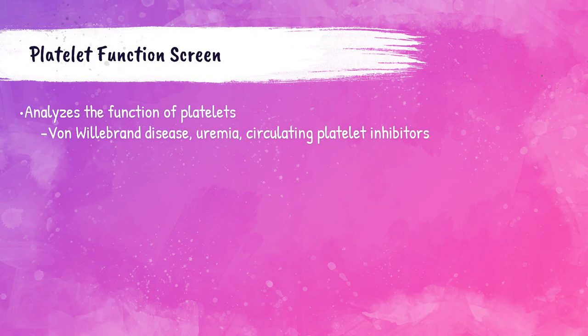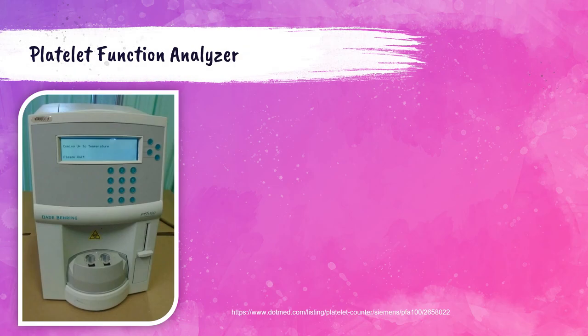The platelet function screen analyzes the ability of platelets to form clots. Abnormalities may indicate von Willebrand disease, uremia, or platelet inhibitors. This is run on a benchtop automated platelet function analyzer that assesses platelet function under shear stress. It uses cartridges containing collagen and ADP, and collagen and epinephrine. The lab technician pipettes whole blood into the cartridges and results are produced within several minutes.